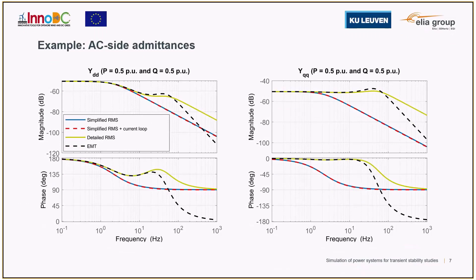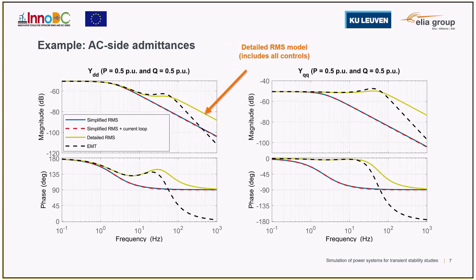We show an example result showing the admittance for all models. For lower frequencies the admittances are the same, and they start to diverge as frequency increases. The black dashed line represents the full-order EMT model and serves as the reference. The most accurate model after the EMT is the detailed RMS in yellow, which includes the same control loops as the EMT. This model follows the EMT up to approximately 10 Hz in the rotating DQ frame, corresponding to roughly 40–60 Hz. This value may also vary depending on control tuning.